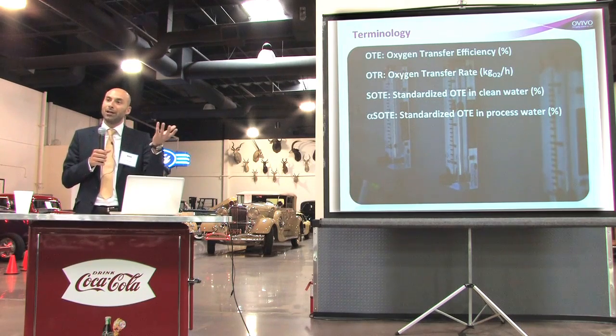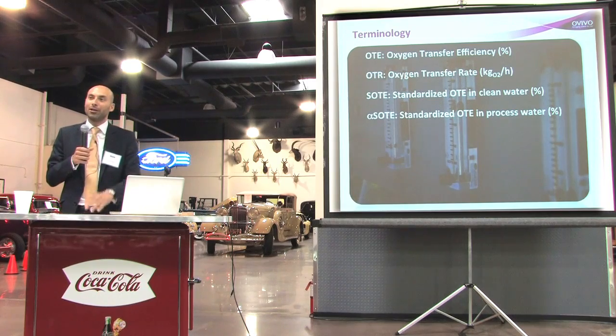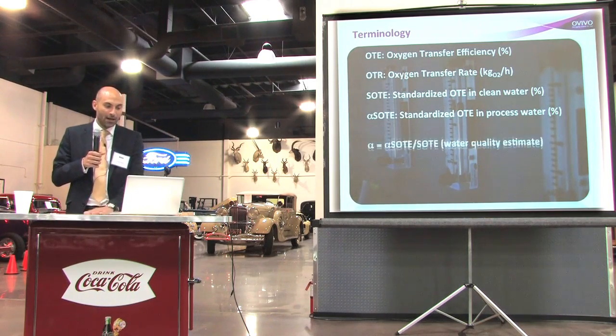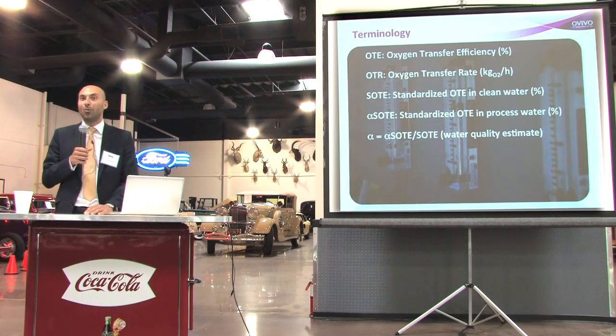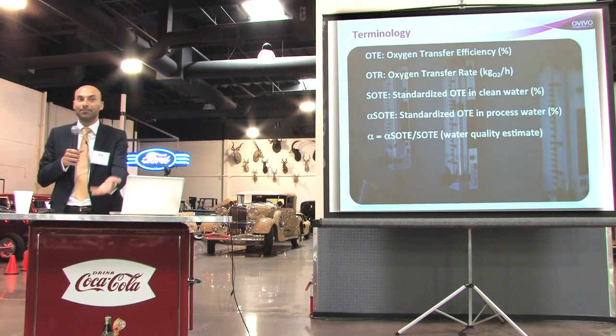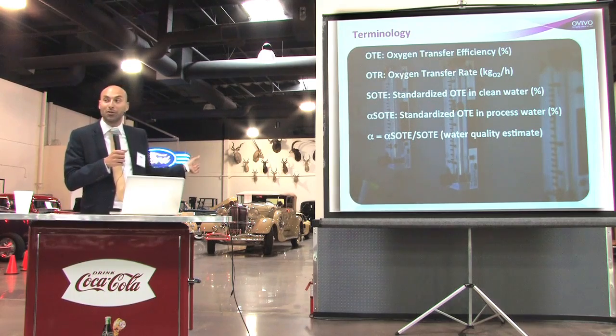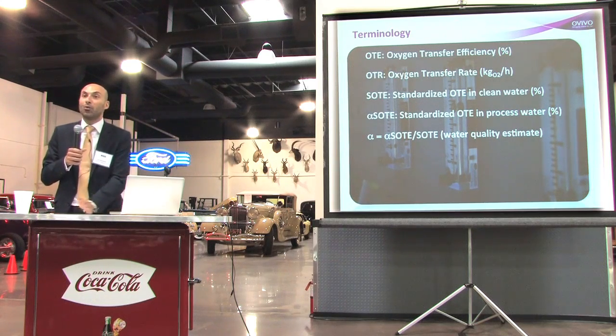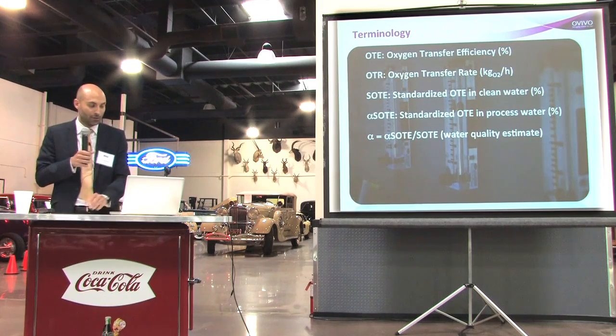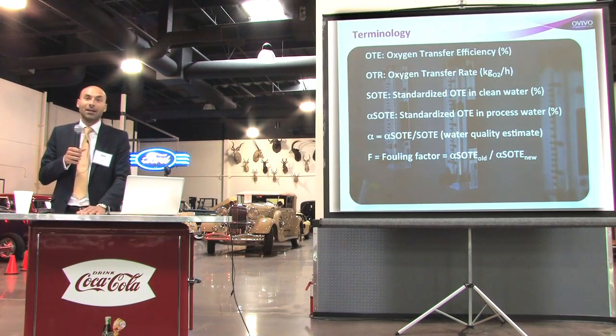As Tom said, we're treating wastewater, not tap water, so we need to scale down performance from tap water. That's where alpha comes in — predicting alpha is nearly impossible before you place a diffuser in wastewater. But once you do, you measure it and ratio it to the clean water value, so alpha becomes a water quality estimate: the ratio of process water efficiency to clean water efficiency.